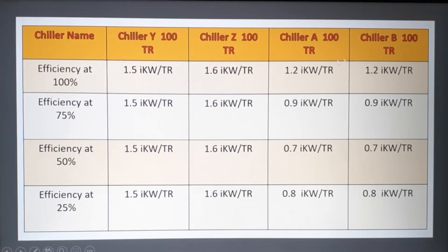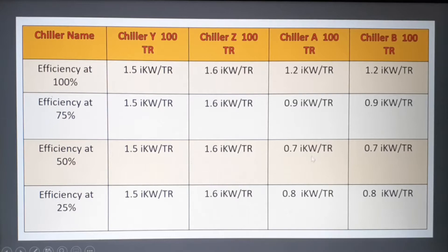For VFD chillers A and B, the efficiency varies with load: at 25% load it is 0.8 kW per TR, at 50% it is 0.7 kW per TR, at 75% it is 0.9 kW per TR, and at 100% it is 1.2 kW per TR. Running the chiller at 50% gives the most savings, as it draws very little power to produce 1 TR. This is what part-load efficiency means — these non-VFD chillers do not have this characteristic.